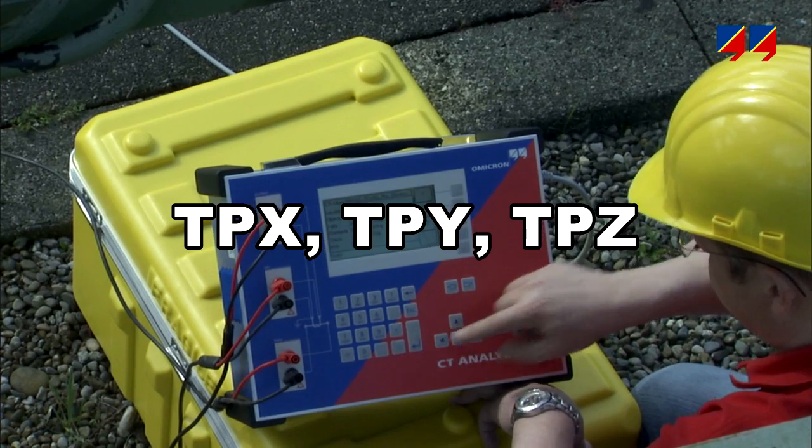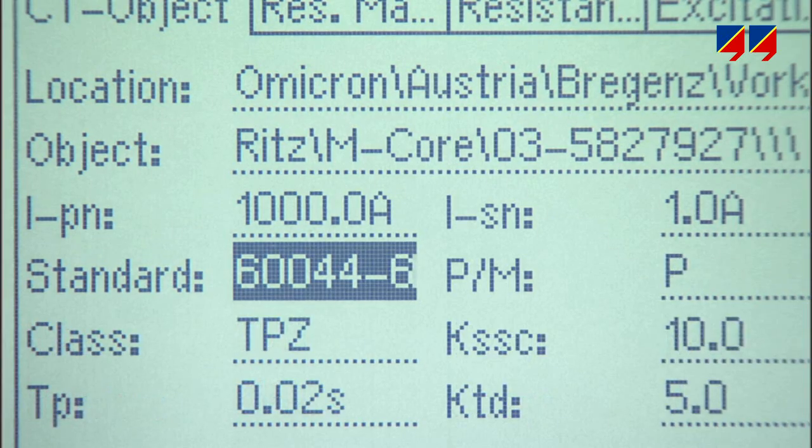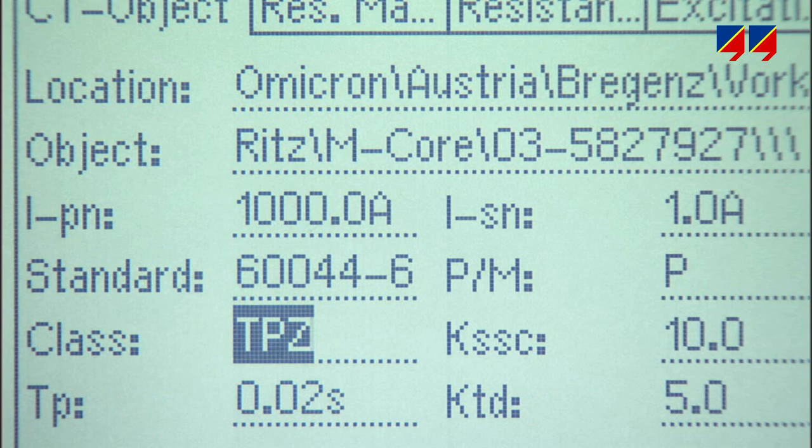These IEC definitions are integrated into CT analyzer, enabling the parameters for TPX, TPY, and TPZ classes to be directly verified.